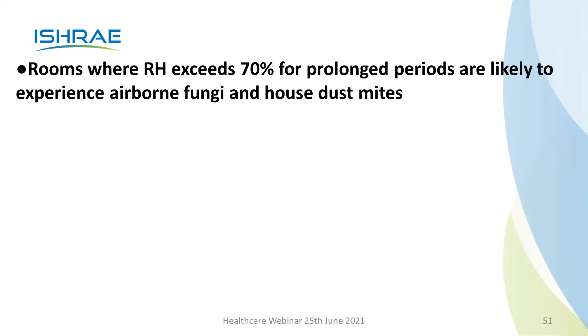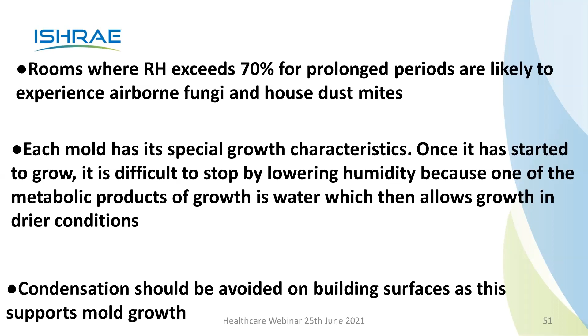Rooms where RH exceeds 70% for prolonged periods are likely to experience airborne fungi and house dust mites. Each mold has its special growth characteristics. Once it has started to grow, it is difficult to stop by lowering the humidity, because one of the metabolic products of growth is water, which then allows growth in drier conditions. That means it is not good enough that, once your RH has been high for a long time and the mold is set in, you reduce the RH. It is of no use, because this mold will only keep growing. Condensation should be avoided on building surfaces, as this supports mold growth.